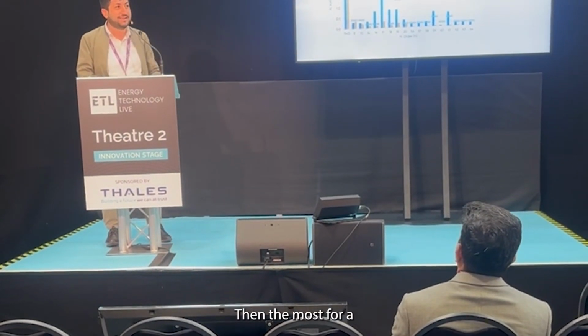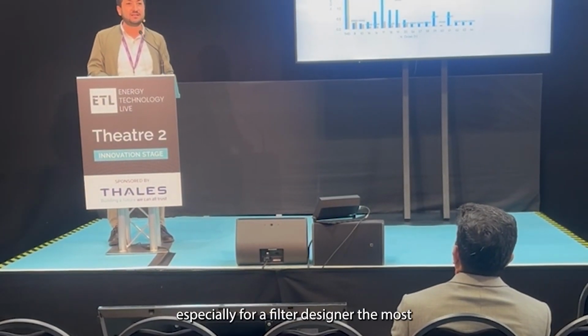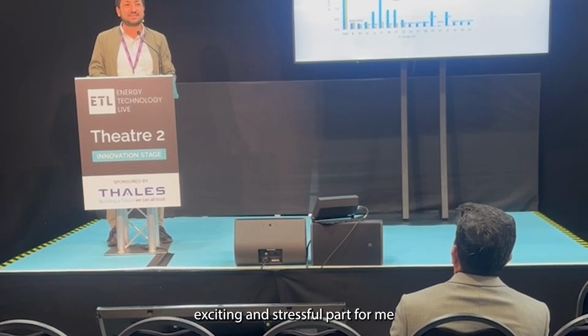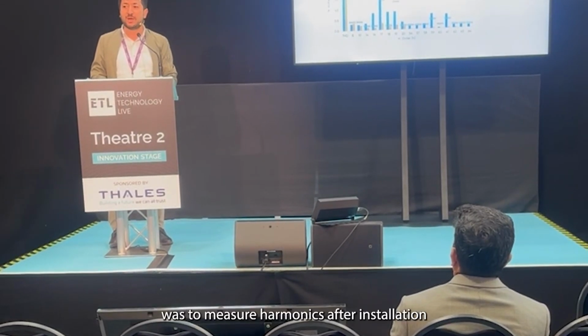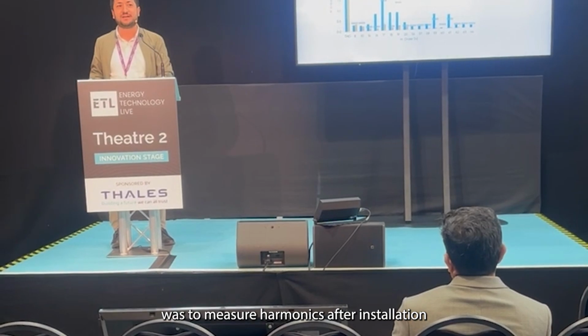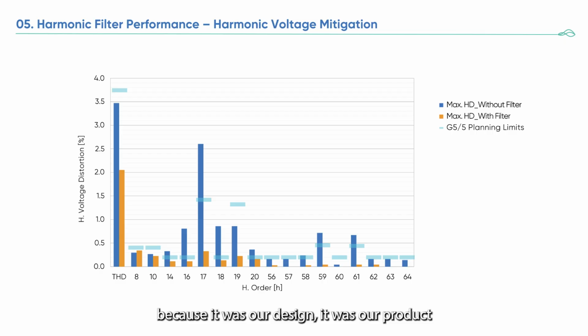Then the most, especially for a filter designer, the most exciting and stressful part for me was to measure harmonics after installation, because it was our design, it was our product, and it was fully our responsibility. We have done post-connection harmonic measurement, and we can clearly see here filter performance. These orange bars, all harmonics orders here are within the G5/5 requirements, so now the site is fully compliant.